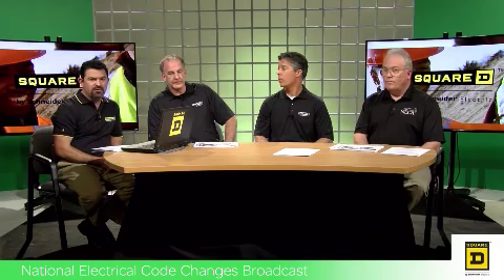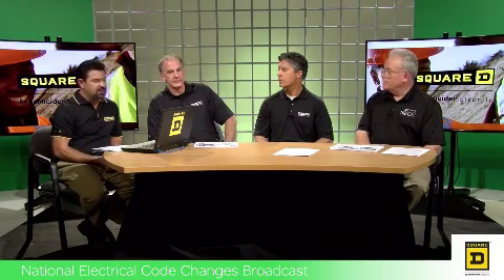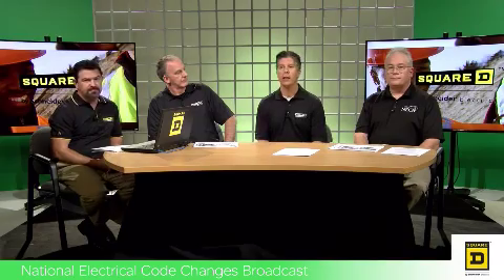Great. Chad, also, can you talk more about performance testing in section 230.95? Okay, so 230.95, we're talking about ground fault protection at the service. So where ground fault protection at the service, 230.95 sets those requirements, and it requires that you test the ground fault protection system for the equipment after it's installed at the site. Now this change adds a new paren C, which is very significant to the electrical contractor because it sets the method of testing as primary current injection only. Now this is going to be impact to the contractor and the manufacturers of equipment equally.